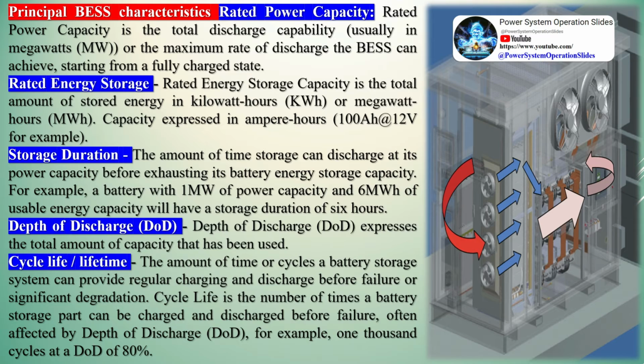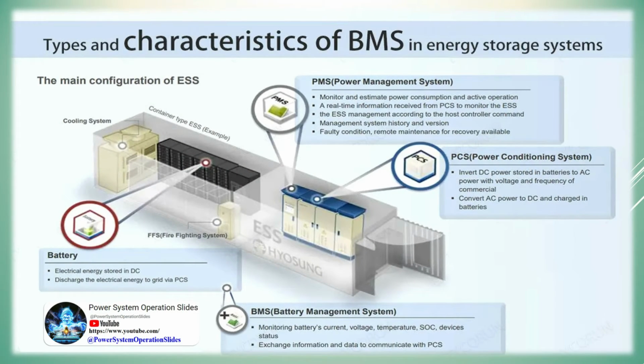Storage duration. The amount of time storage can discharge at its power capacity before exhausting its battery energy storage capacity. For example, a battery with 1 megawatt of power capacity and 6 megawatt-hours of usable energy capacity will have a storage duration of 6 hours.